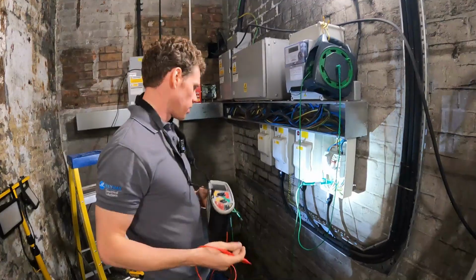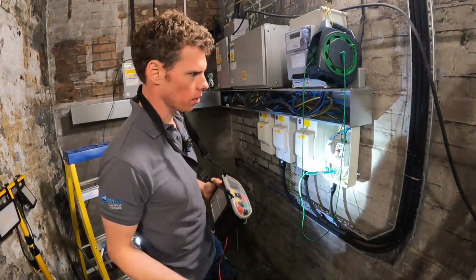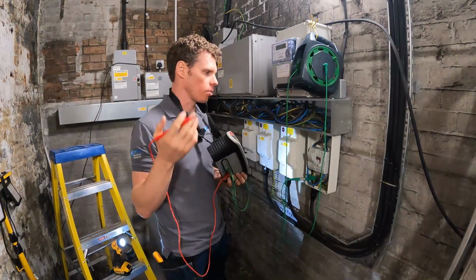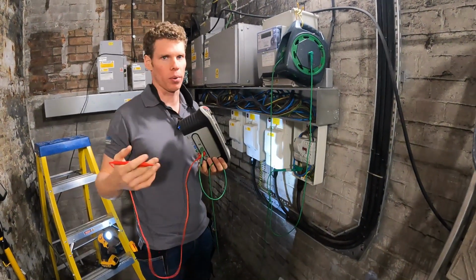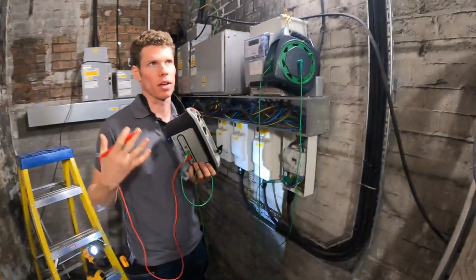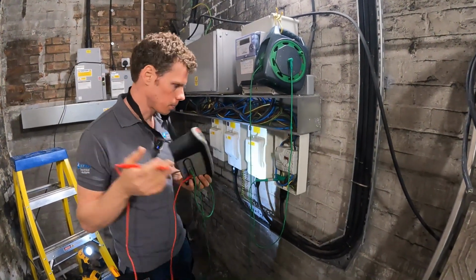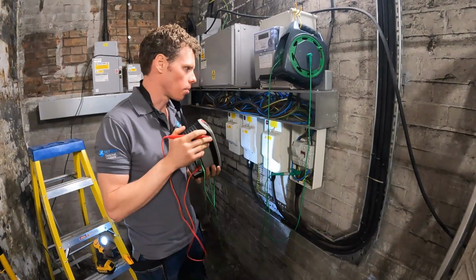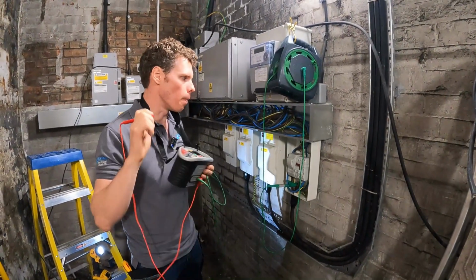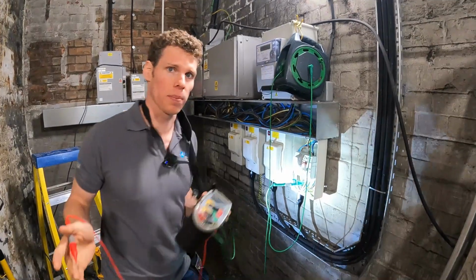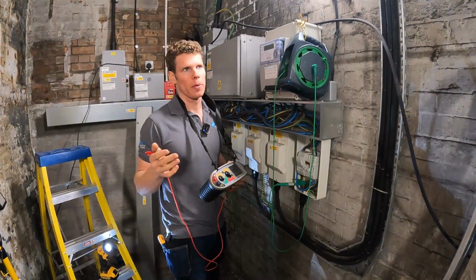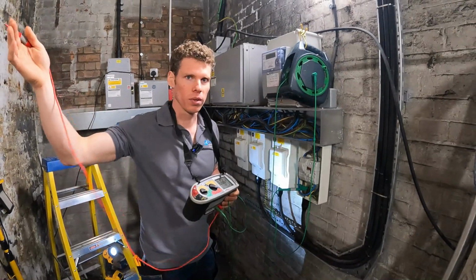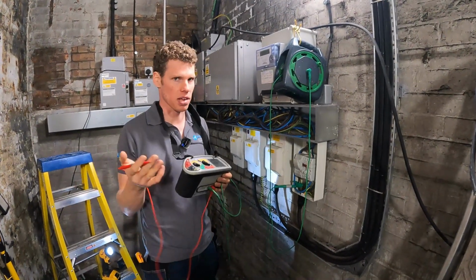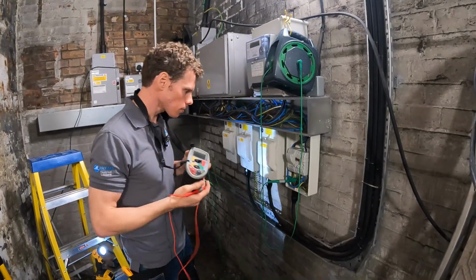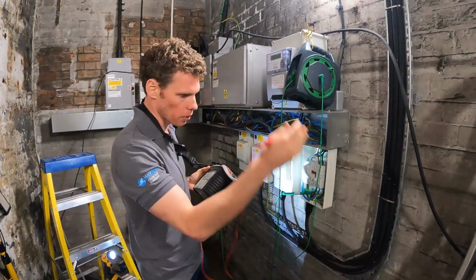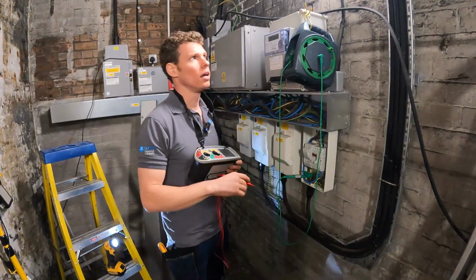Right, starting at the beginning - if you haven't done an R2 wandering lead test before, get in the habit of doing it. It's really quick, really easy, and gives you great reassurance that things are protected by an earthing conductor, especially in installations like this with the old Crabtree boards. Because if it wasn't for the conduit hanging off the wall, I'd be happy to pass this so long as everything was earthed.